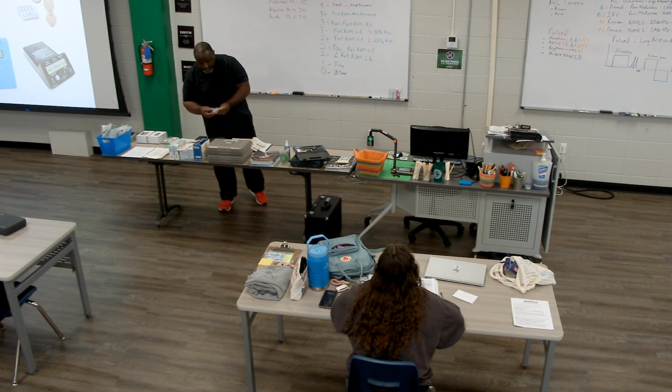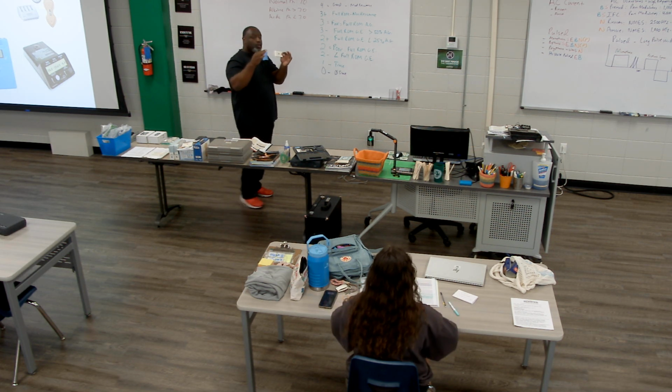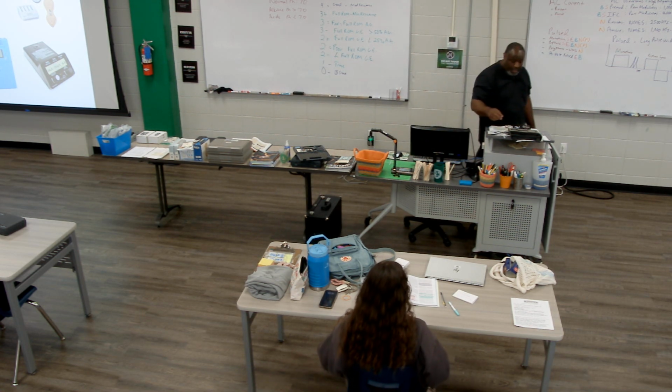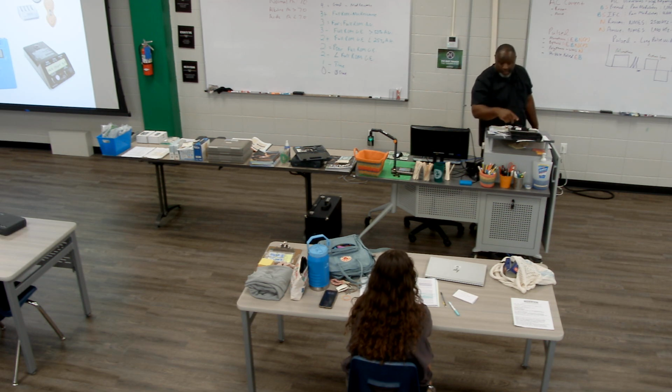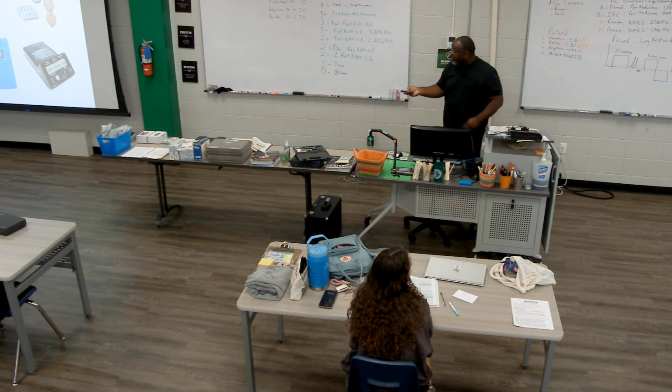So that's one. Here's the treatment one. So these are the two we would use. This is our old one. So this is a dispersive, meaning it's just providing current and being out of the way. This is our active electrode here. And they both have these pins on the back where the electrode will connect to our device. So that's how we would get iontophoresis introduced. So that's a unit like that. Sometimes you may clinically still see this unit here. So that's it there.